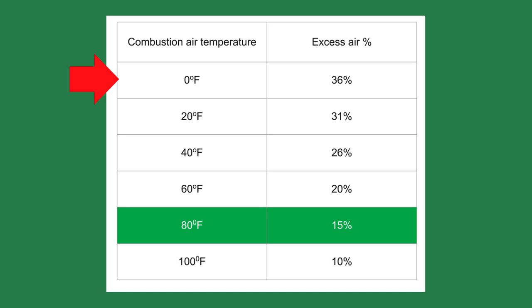As the cold weather moves in and the temperature drops to zero degrees outside, the excess air rises from 15 to 36 percent — 140 percent higher. This reduces the boiler efficiency to 83.1 percent. It's less than one percent, so it's no big deal, I can hear you say.